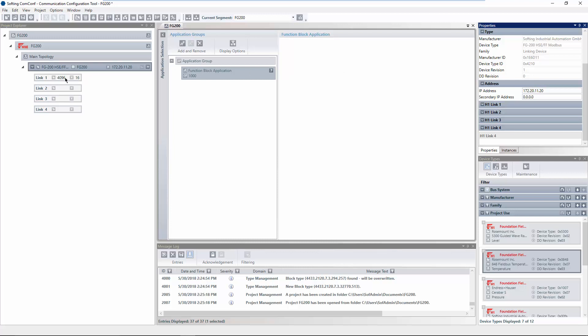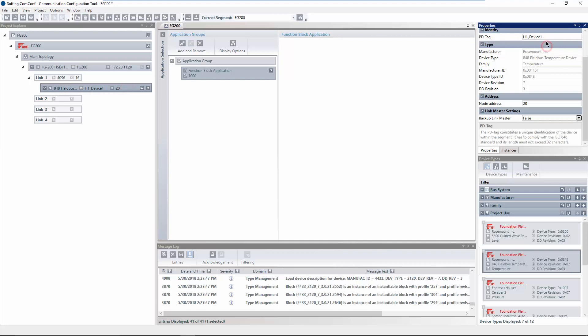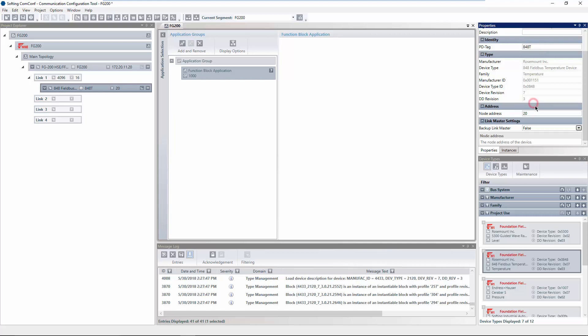In the project explorer, select the link the device is connected to and add the device by clicking on the plus symbol of the corresponding device type in the window device types. Select the added FFH1 device and adapt the PD tag and the node address in the properties window. If required, the FFH1 device can be configured as backup link master.